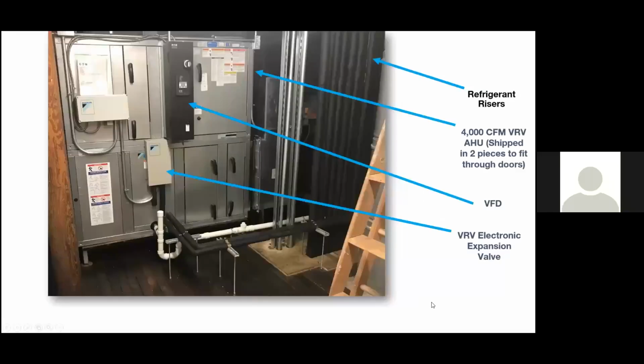And then just looking at a final install pic here of the air handlers with these VRF integration kits, you can see on the right here, or kind of in the middle, we have the expansion valve that was field installed. And as I mentioned, you can now get these factory installed as well. You can see the piping going in and out of it. Then we have the variable frequency drive, or the VFD, on the fans to modulate the airflow to the space.